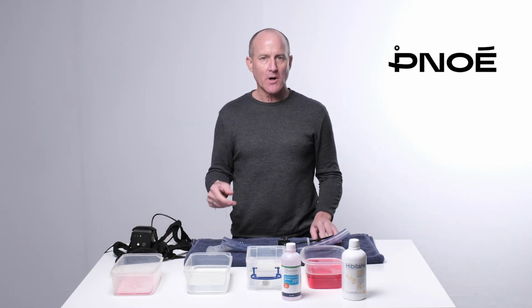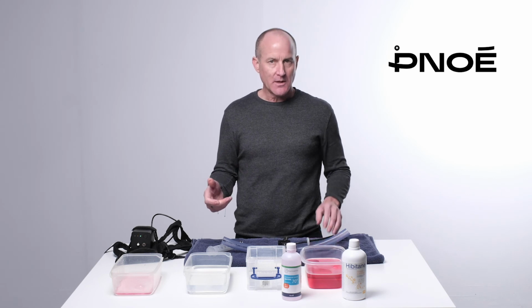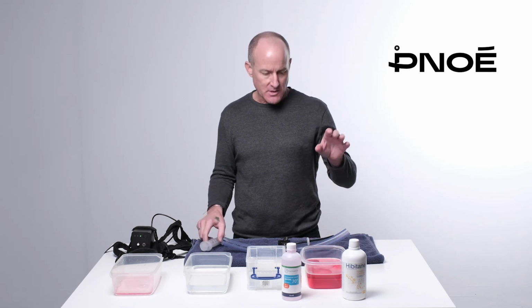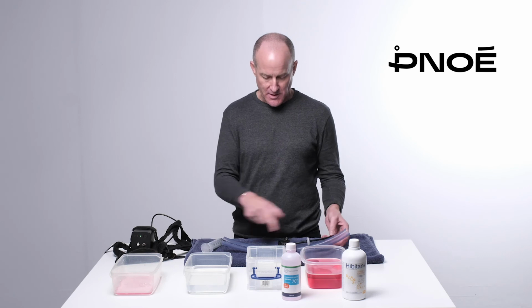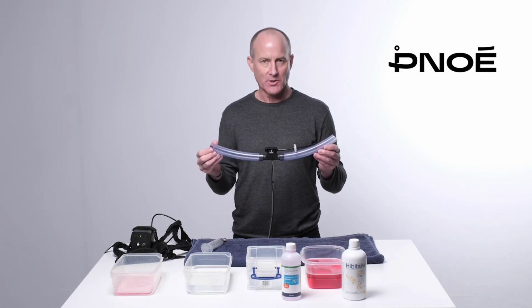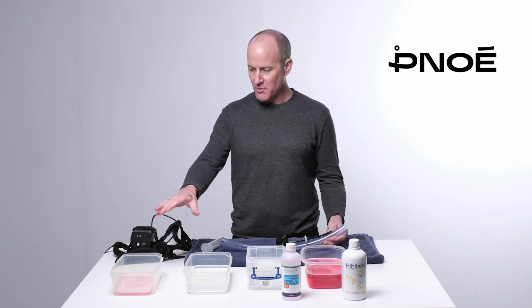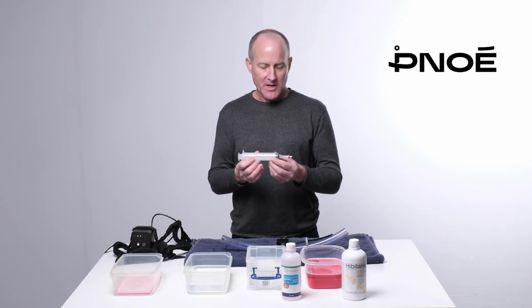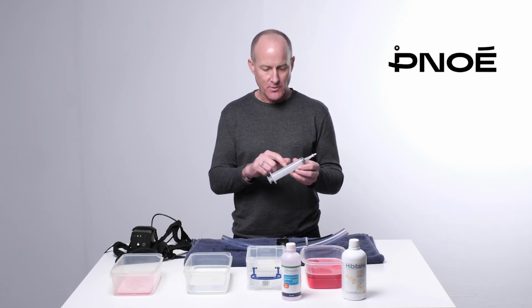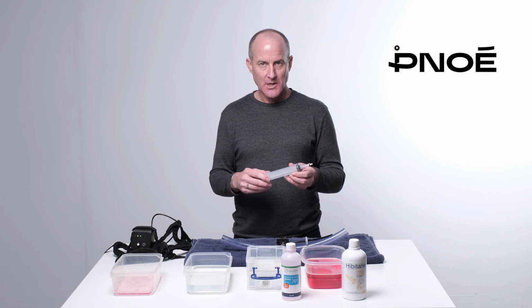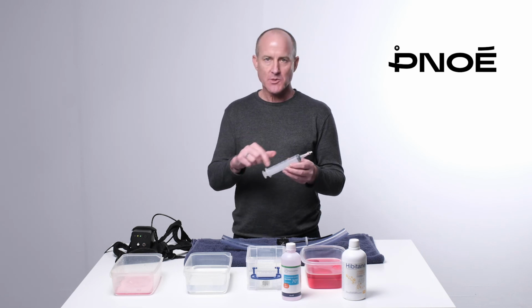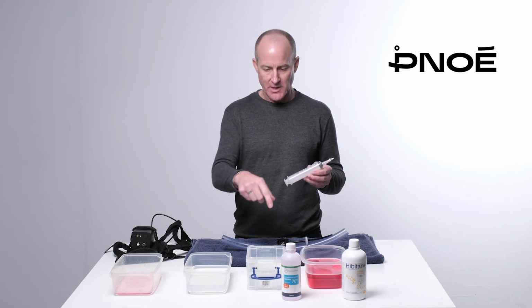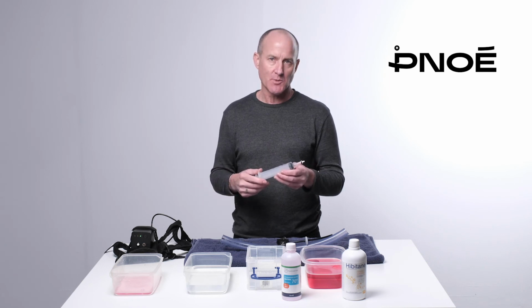It's important to note, unlike the mask cleaning, you're going to only use that solution once with the flow sensor cleaning. And these will be thrown out. I recommend that between using your syringe and the different solutions, you always rinse the syringe between each one with deionized water as well.